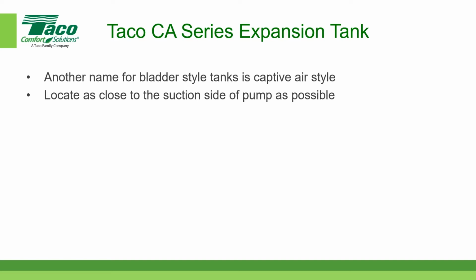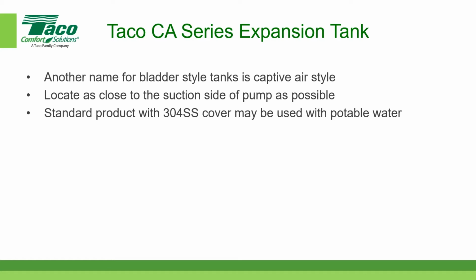Rich made this comment when he talked about expansion tanks, and it should be in your detailed drawings - it should be located as close to the suction side of the pump as possible, at least that connection. That's the lower pressure change, and that's the reason why you want to do that.